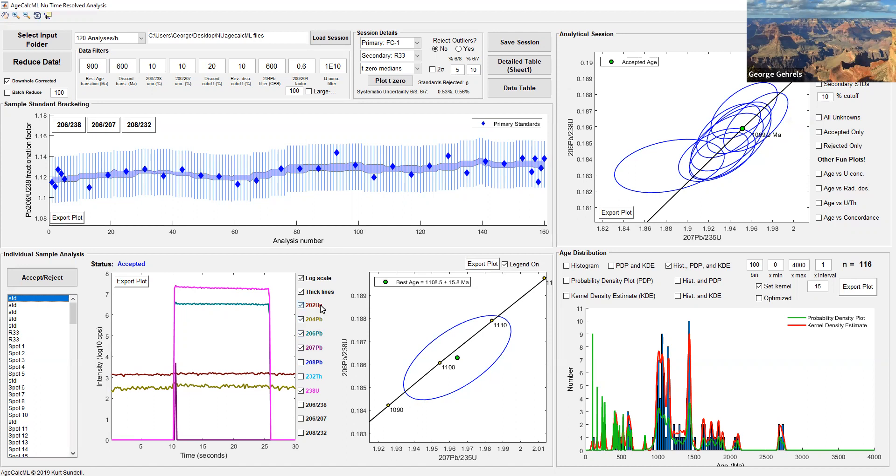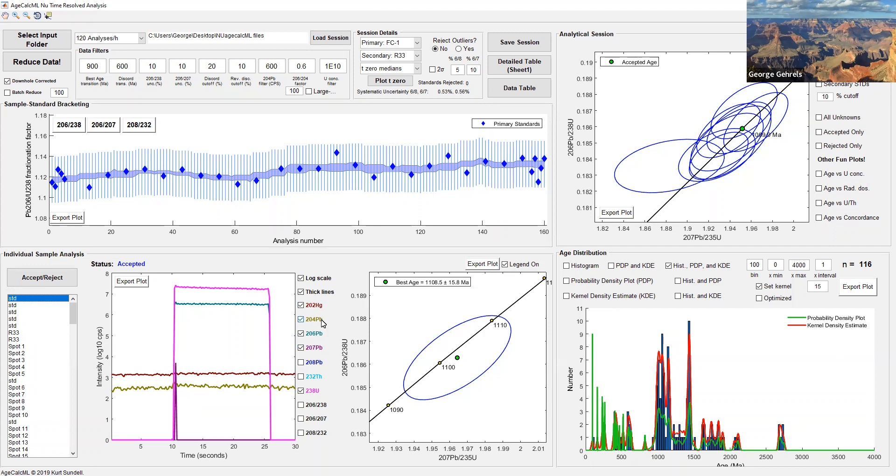We also look at 204, the non-radiogenic isotope of lead. This is the one that tells us how much lead was in that crystal at the time of crystallization, and this 204 intensity is very small. We measure these with ion counters rather than Faradays because they're able to measure very small ion intensities. We also measure mercury 202 because there's an isotope of mercury at the 204 position. We take the total 204 measured, subtract the 204 mercury, which we get because we know the 202-204 ratio of mercury in nature, and we end up with 204 which is only the lead isotope. Then we can do that initial lead correction.